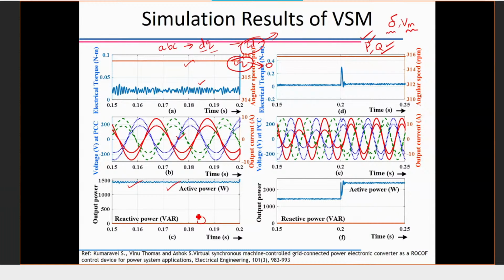The main beauty of the virtual synchronous machine is that you can make the machine operate in any quadrant, meaning any combination of real power and reactive power. So if you want to inject real power and reactive power into the grid, yes, it is possible.